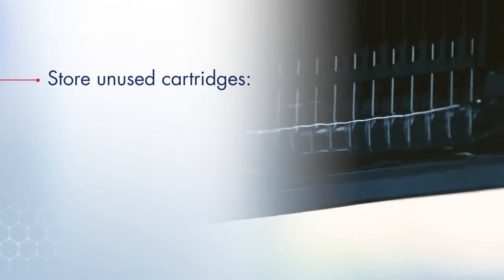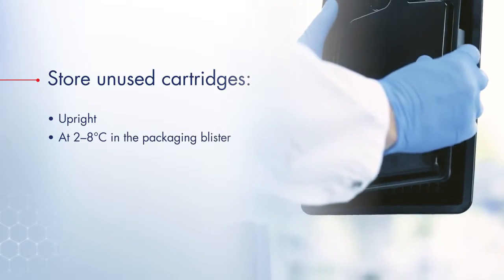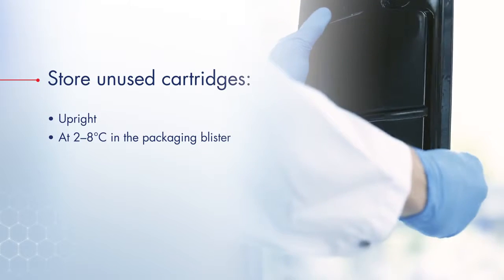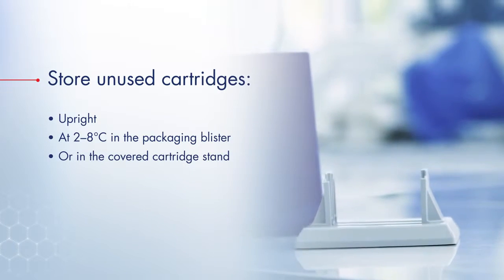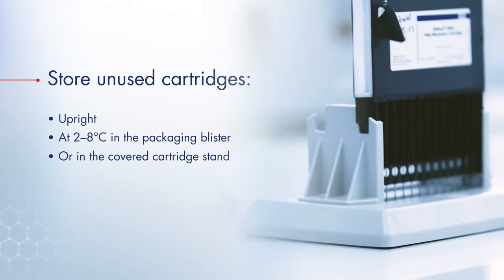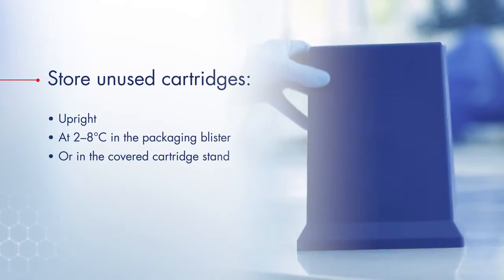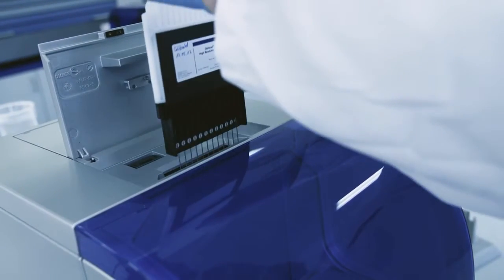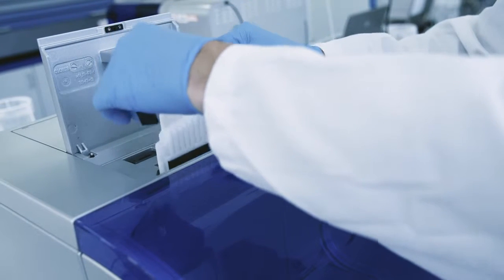Unused cartridges should always be stored upright at 2 to 8 degrees Celsius in the packaging blister or in the covered cartridge stand to protect the gel in the cartridge from drying and from direct light. If the cartridge is stored in the QIAxcel Advanced, the instrument should always be switched on.